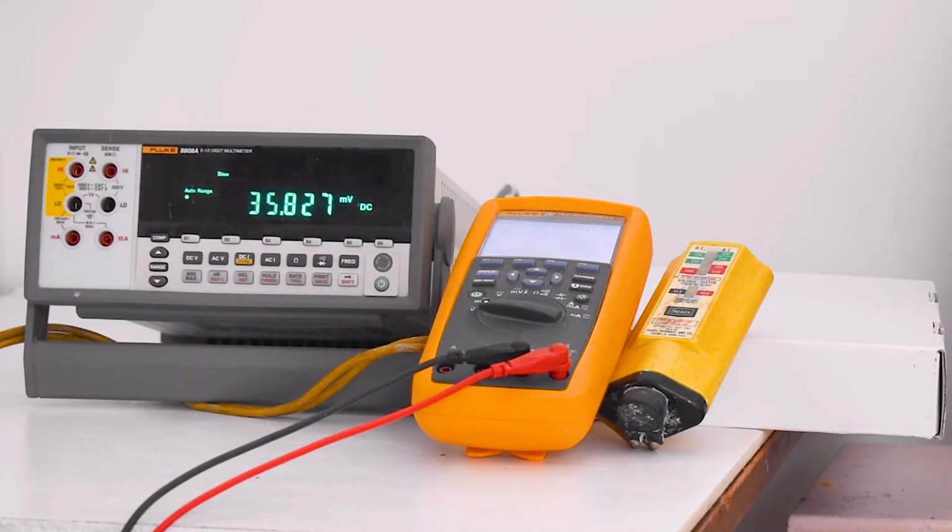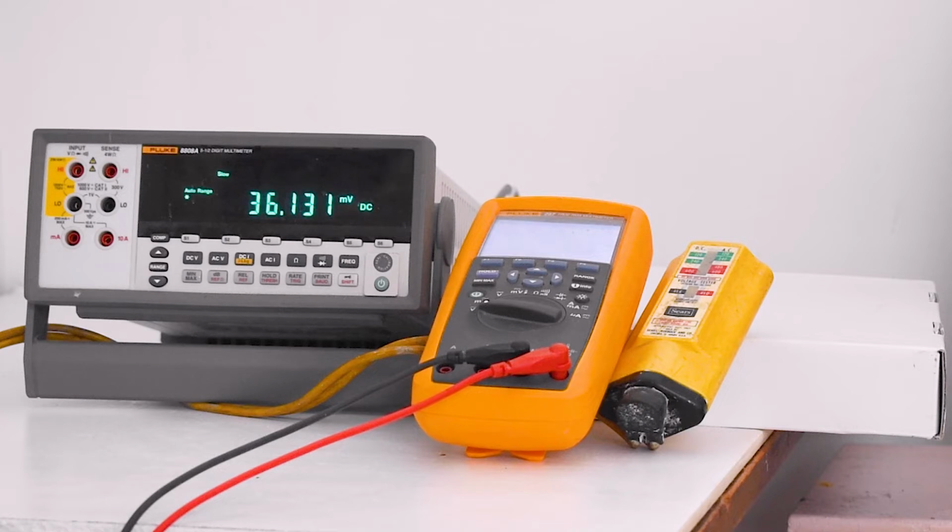Notice that the readout fluctuates either side of the 0.03 volts reading. This is puzzling to beginning students and apprentice electricians. It is known as phantom voltage, a consequence of the fact that the meter is auto-ranging and very sensitive. The fluctuating voltage is analogous to the noise floor we see in an oscilloscope or spectrum analyzer. The floating voltage is also a consequence of the fact that the probes are not connected to anything.